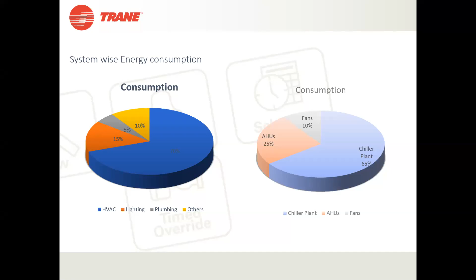So what does it do? This is a simple diagram, let me use the pointer here. Just give me a moment. So in this basic diagram, these are the primary pumps, these are the secondary pumps, then you have the condenser pumps, then you have the cooling tower, and you have the chillers. On this side, secondary pumps lead to FCU, AHU, and all other systems here. So you can understand this is a very complex system.